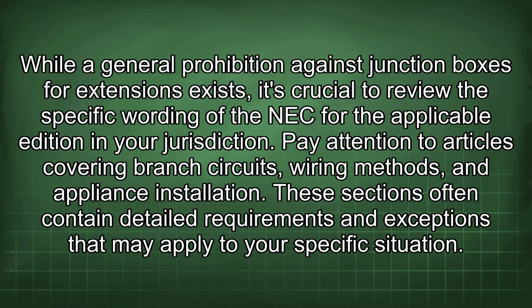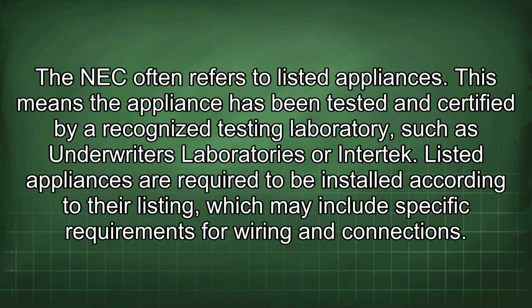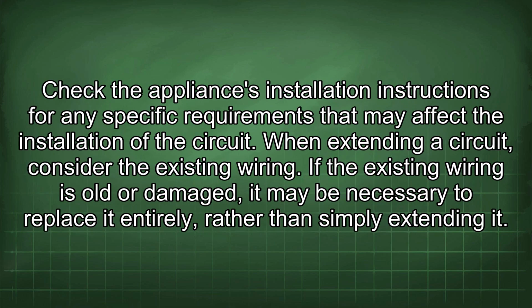Pay attention to articles covering branch circuits, wiring methods, and appliance installation. These sections often contain detailed requirements and exceptions that may apply to your specific situation. The NEC often refers to listed appliances. This means the appliance has been tested and certified by a recognized testing laboratory, such as Underwriters Laboratories or Intertek. Listed appliances are required to be installed according to their listing, which may include specific requirements for wiring and connections. Check the appliance's installation instructions for any specific requirements that may affect the installation of the circuit.